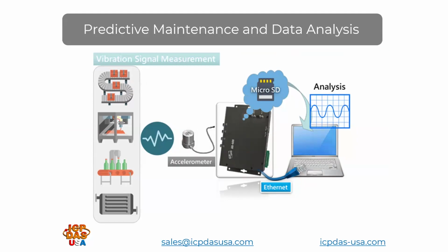Predictive maintenance and data analysis. Vibration analysis allows engineers to assess the condition of devices such as pumps and motors. By continuously gathering data on vibrations, engineers can predict when equipment needs maintenance. Vibration data is easy to gather and is very effective at identifying problems in equipment that use motors.